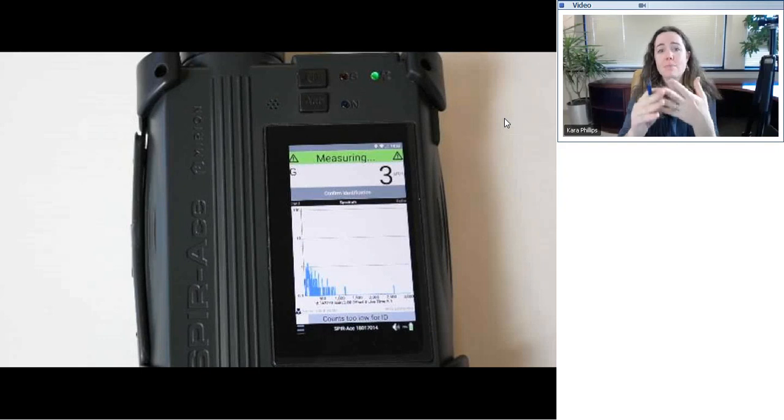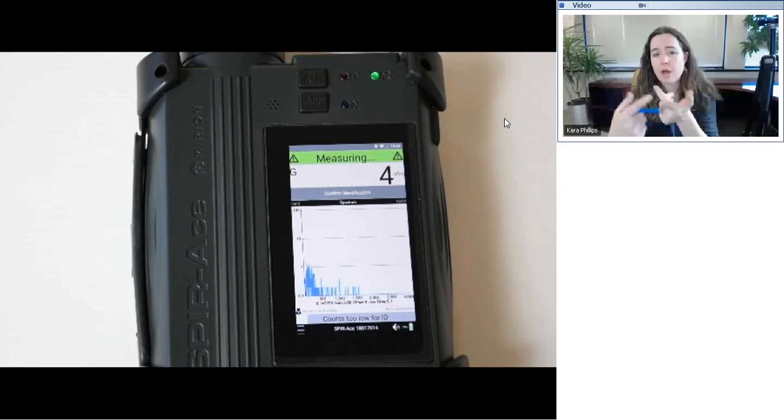And that's going to have embedded in it the spectral data, including the count time, the counts and all the other information we need with the spectrum, as well as that text string. So I have a record of the sample information to help identify it later, and also that embedded efficiency or geometry file. So I can very easily collect and analyze that measurement when I have it on my Genie system.